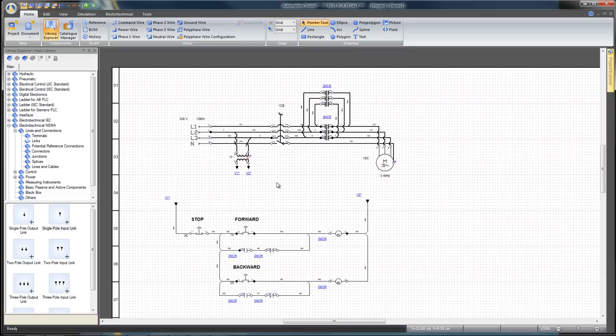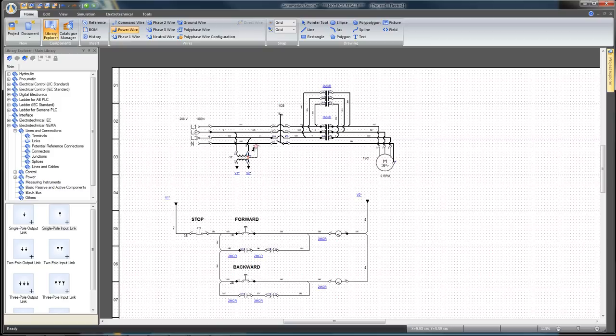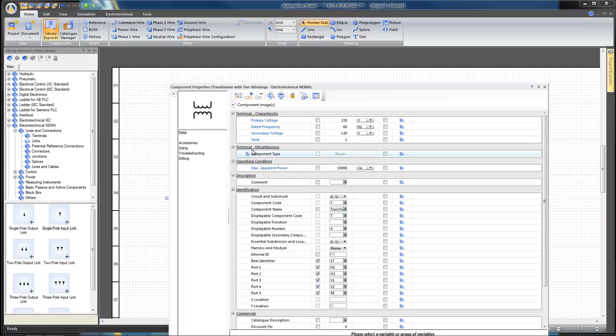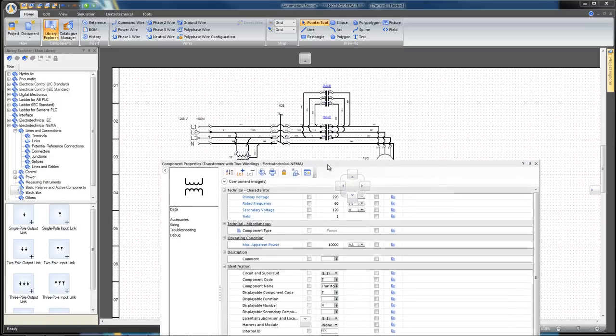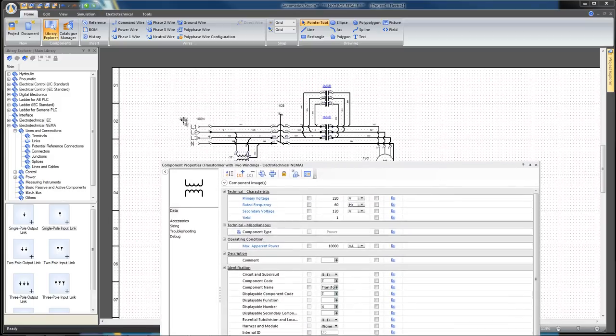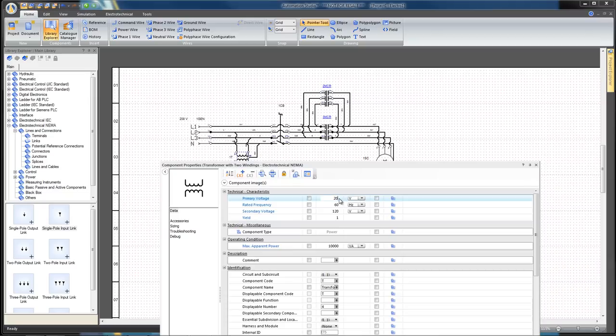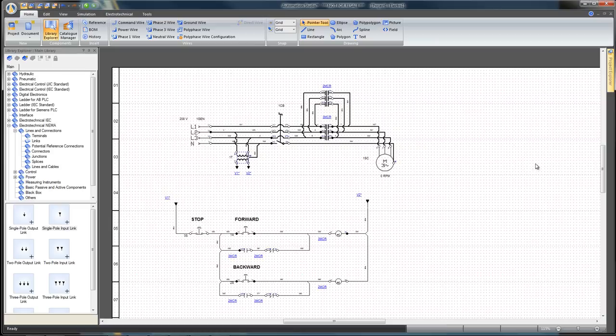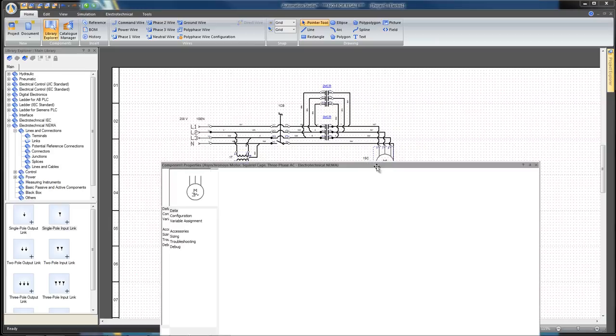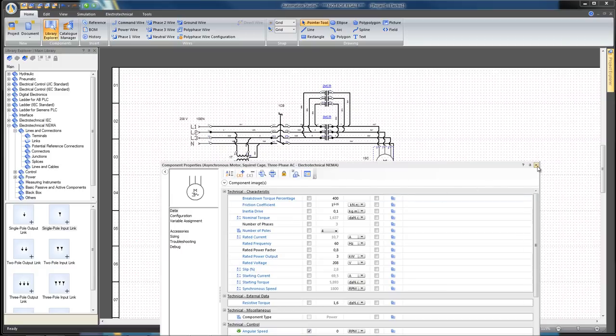Connect the neutral from the transformer to the source neutral and double-click on the transformer to verify primary and secondary voltages. As the primary voltage is different to the three-phase source voltage, you can change it to 208 volts by typing this value in the corresponding box. Double-click on the three-phase motor to verify that the rated voltage is also 208 volts. In this case, it's OK.